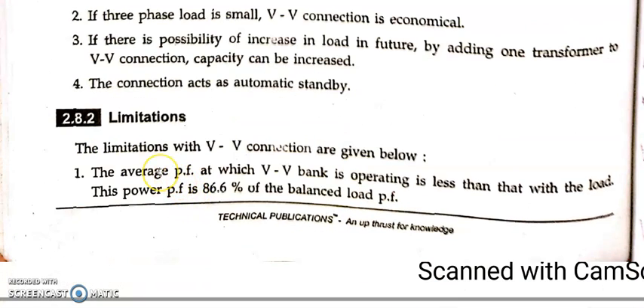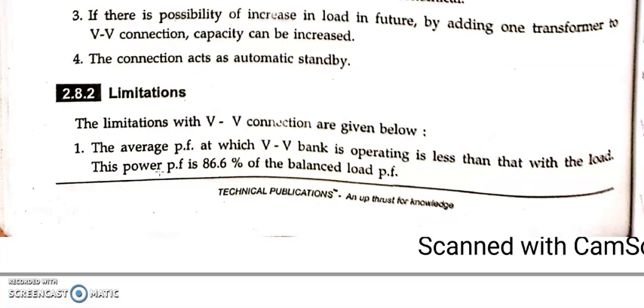So coming to the limitations, the first limitation you can see here is the power factor at which your VV bank is operating. Now let us see the limitations. At first, we know that the average power factor of the open V connection or open delta connection will be less than the load power factor. Usually the power factor is around 86.6% of the balanced load power factor. Okay, here the power factor of VV connection is less. That is what you need to remember.